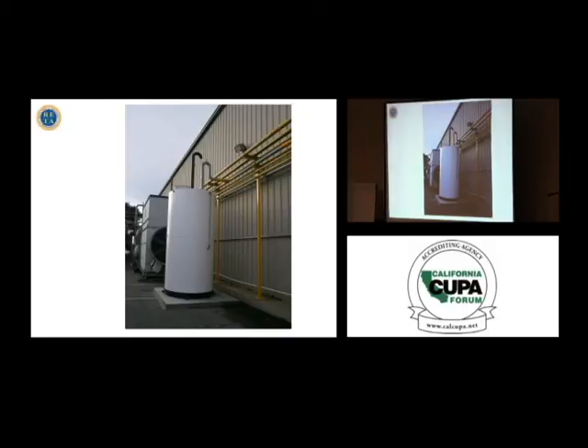But you want to make sure that you always have at least the right amount. My rule of thumb is on my vertical tanks, it's 5/8 full of water. That's the standing quantity. And how much is there is a calculation of size of your relief valves, etc.